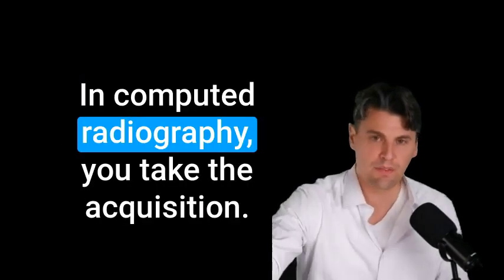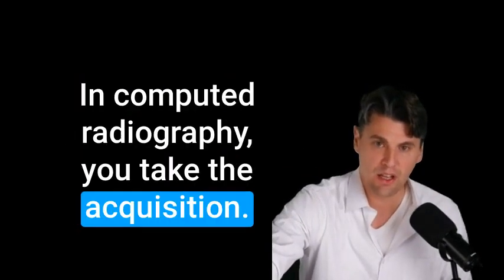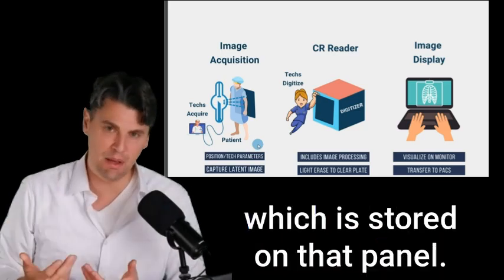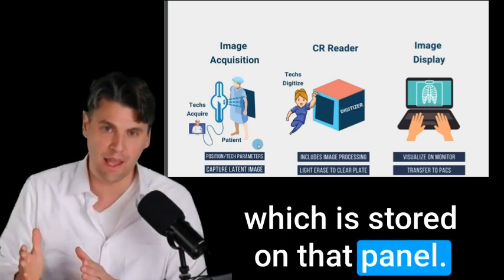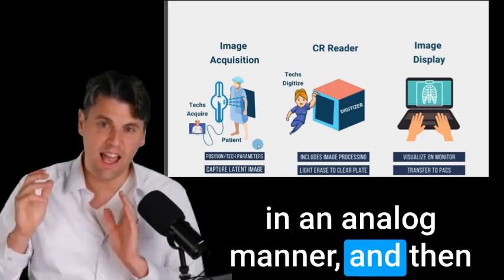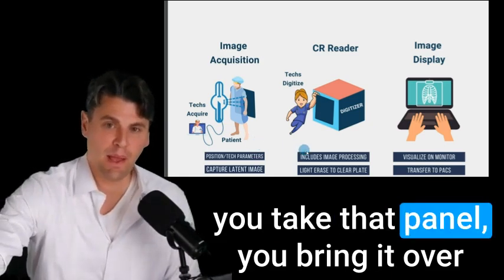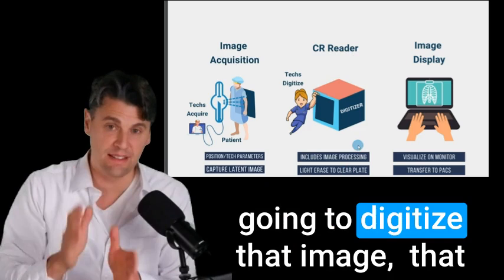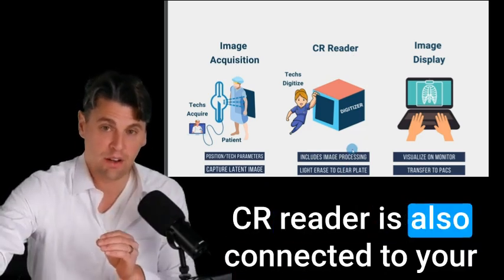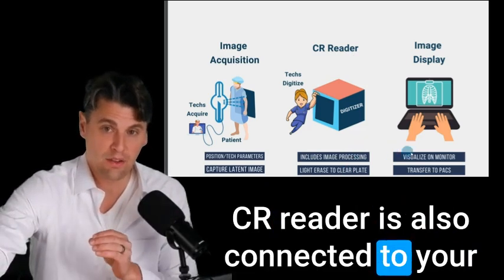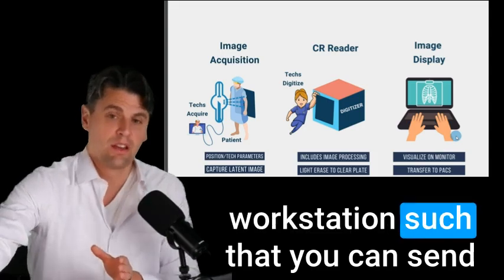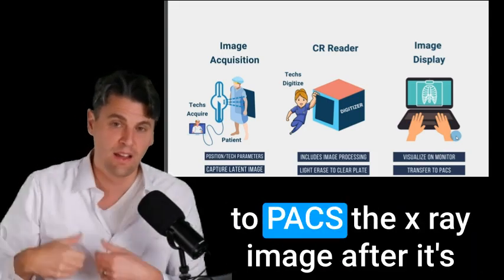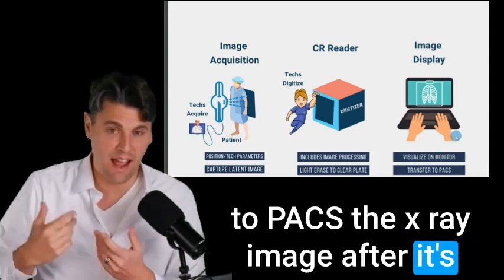In computed radiography, you take the acquisition. There's then a latent image, which is stored on that panel in an analog manner. And then you take that panel, you bring it over to a CR reader. That CR reader is going to digitize that image. That CR reader is also connected to your workstation such that you can send to PACS the x-ray image after it's been digitized.